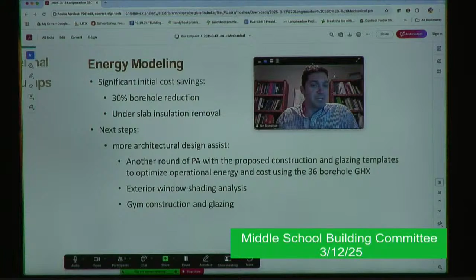Thanks for hanging in there with me, guys. Basically the takeaway at this phase of the energy modeling is that we're showing at least a 30% borehole reduction, which is a significant amount of cost savings. Just by going through our design process, it's going to be better than somebody who might just use rule of thumb metrics or design day calculations without going through this whole detailed model. We've also determined to remove under slab insulation, which will be another nice initial cost saver.